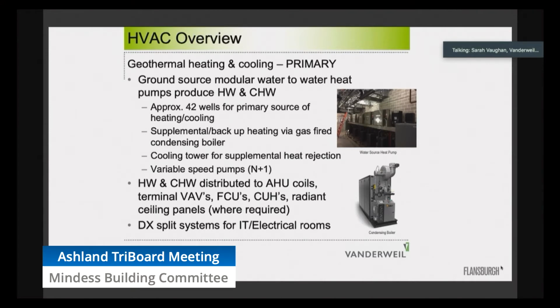And then for the peak times, which occur much less frequently, we have supplemental systems. We'll have a supplemental gas-fired boiler to get to the peak heating, and a cooling tower for supplemental heat rejection for peak cooling. All of our hydronic systems will use variable speed pumps with VFDs to allow for demand response. All the pumps will be N+1, so that if a pump is ever down for maintenance, we have an additional pump and you don't lose capacity in the system.